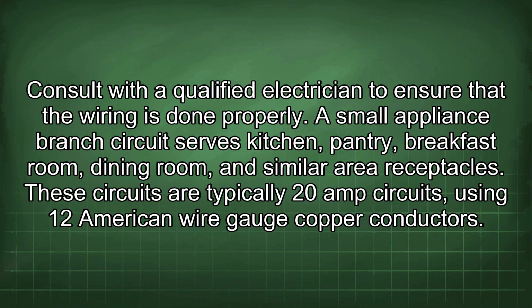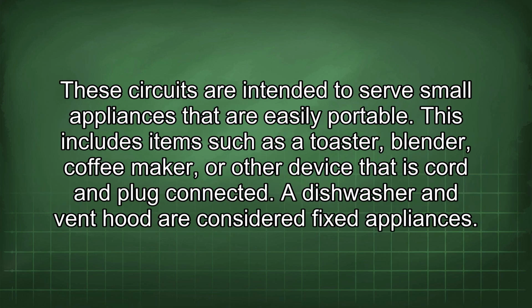A small appliance branch circuit serves kitchen, pantry, breakfast room, dining room, and similar area receptacles. These circuits are typically 20 amp circuits, using 12 American wire gauge copper conductors. These circuits are intended to serve small appliances that are easily portable. This includes items such as a toaster, blender, coffee maker, or other device that is cord and plug connected.